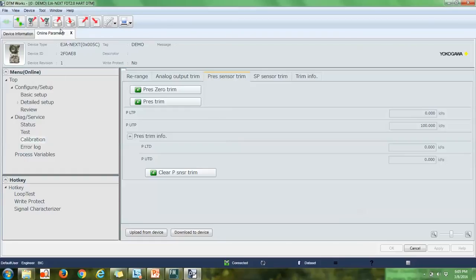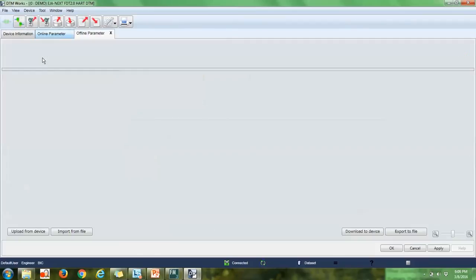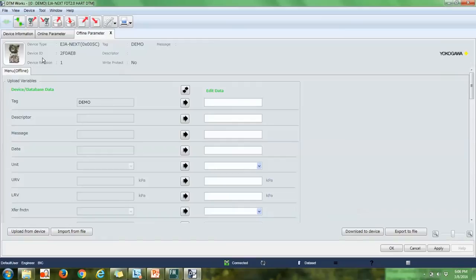One last feature I want to show you with Fieldmate is saving configuration files. All of this part of Fieldmate has been in the online menu, this online parameter screen, so every adjustment I've made or would have made is happening in real time because I'm connected to the transmitter. What we can do is go to Device and Offline Parameter and make adjustments offline. I've got this workspace here. Again, we're offline, so nothing except the tag has been populated. So I want to upload from my device, which will get all the variables from the transmitter I'm connected to.